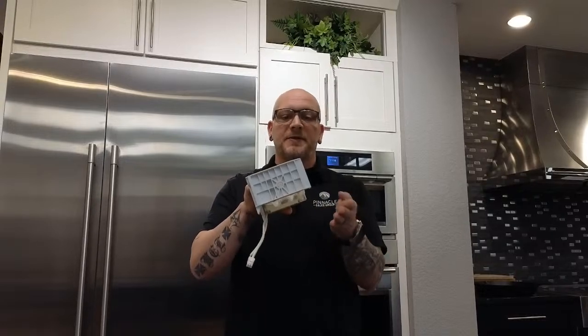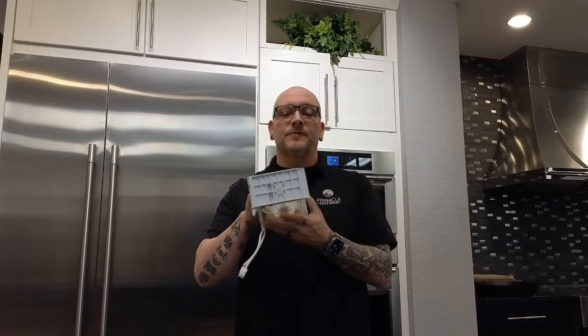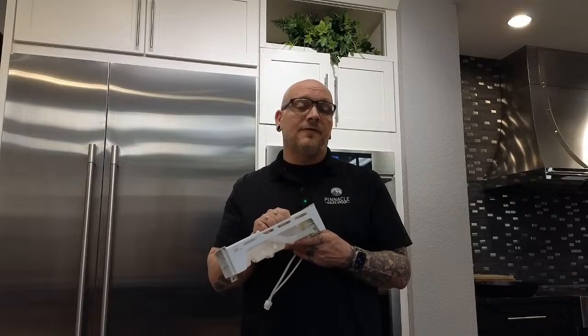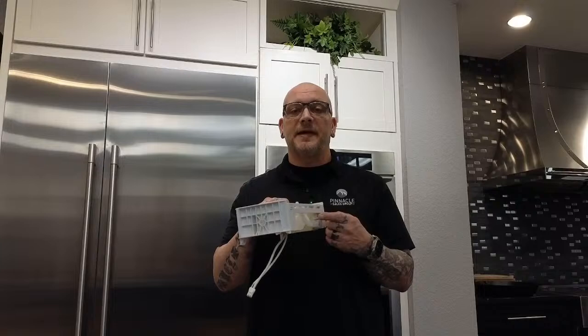Along with pressurizing the system, you go into manual clean and you actually hit the start button. It'll rotate the ice maker. The ice maker harvests, so you're checking ice maker functionality, and it rotates back home. That way you're going to determine if the ice maker physically passes or fails that check. If the ice maker does not rotate, you may have a bad ice maker or you may not have voltage from your main board.